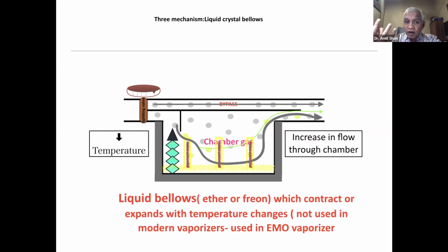So this liquid, ether or freon, will contract with the reduction in the temperature, which will allow a larger flow to pass through the chamber. So that's a liquid crystal bellow, which is not used in the modern vaporizer. It was mainly used in the EMO vaporizer, which you have seen. The liquid crystal bellows were used in the EMO vaporizer, but over time it can fracture, the liquid can be lost, and some other problems were there. So it is not used now.